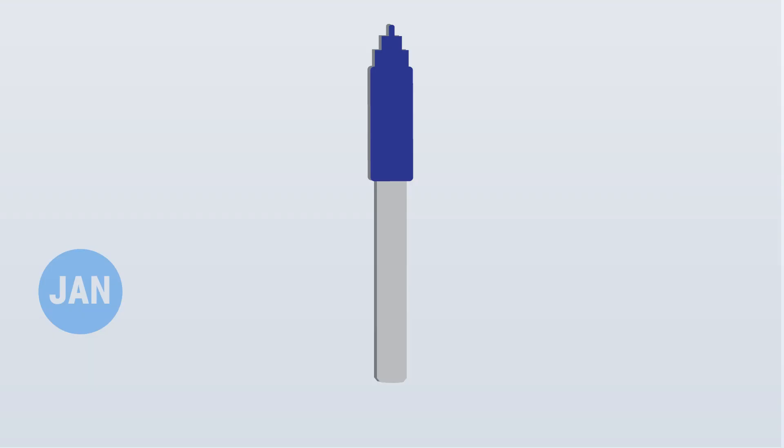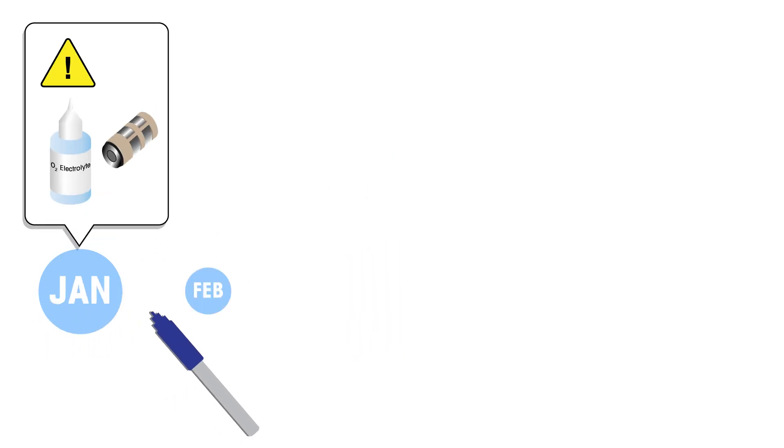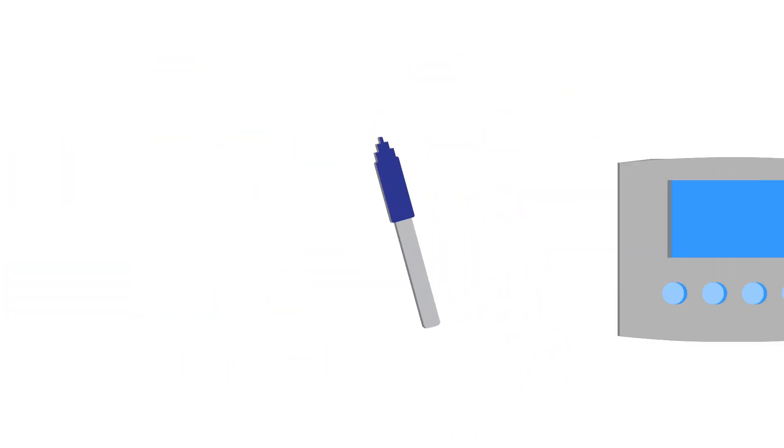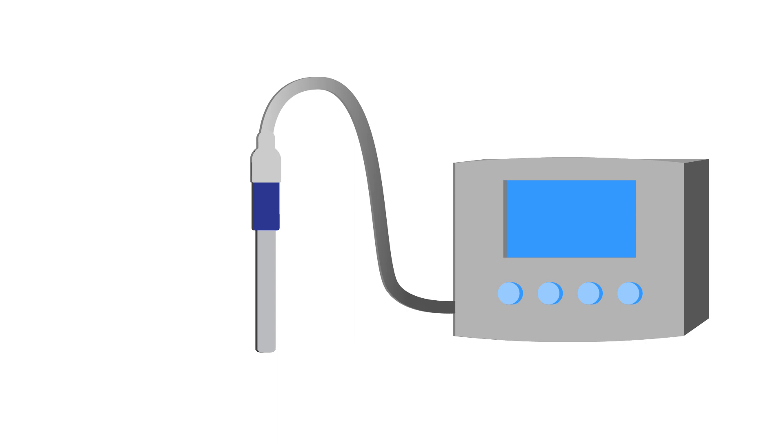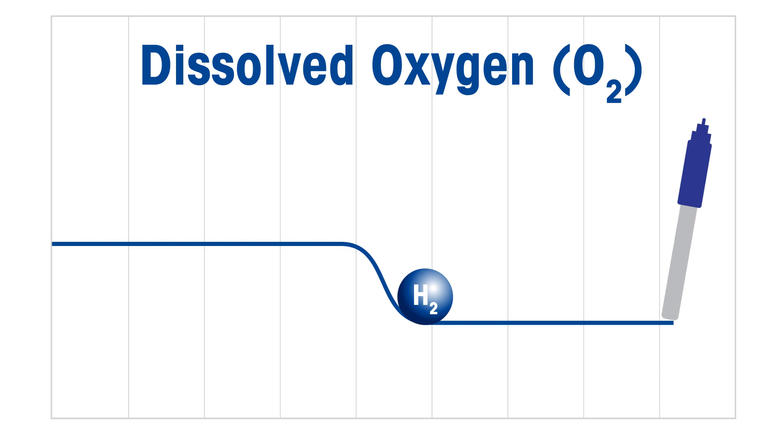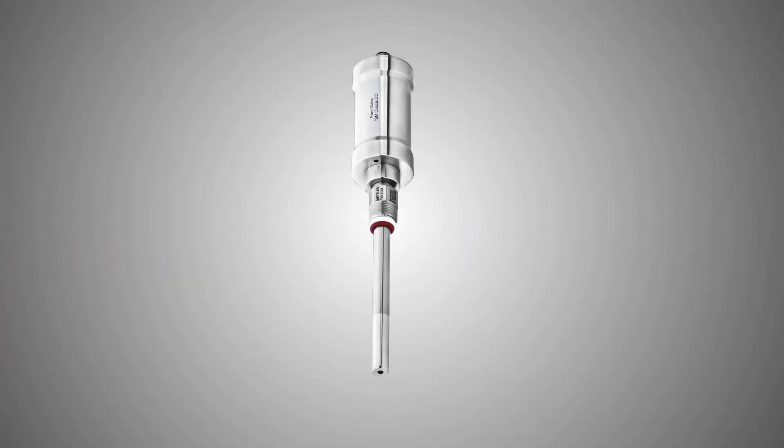Depending on the operating environment, polarographic sensors can require monthly electrolyte and membrane replacement. After service, the sensor cannot produce meaningful readings for several hours because of required polarization. They are also sensitive to sample flow rate and experience interference from dissolved hydrogen.